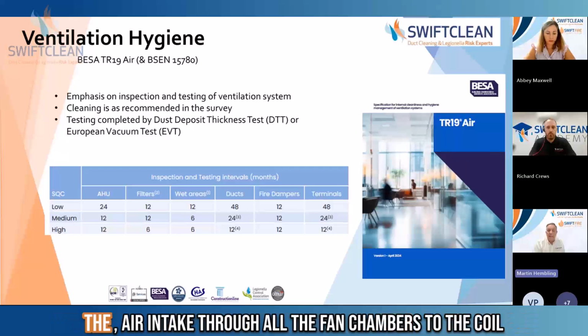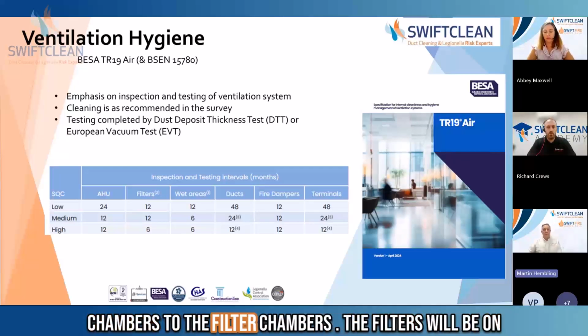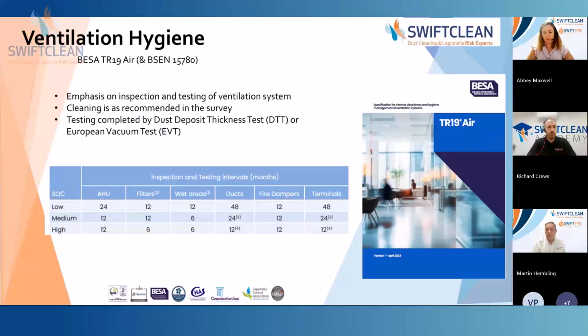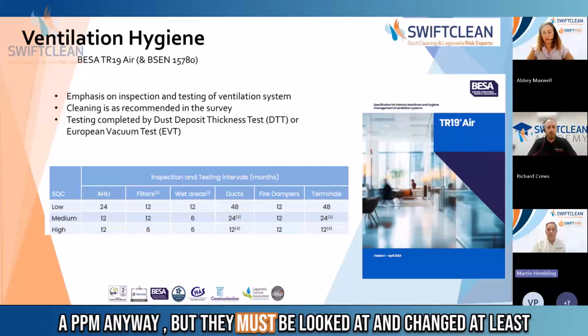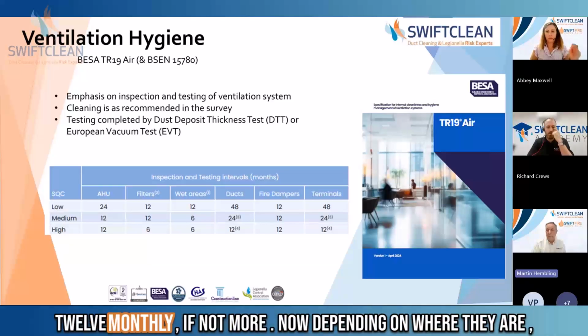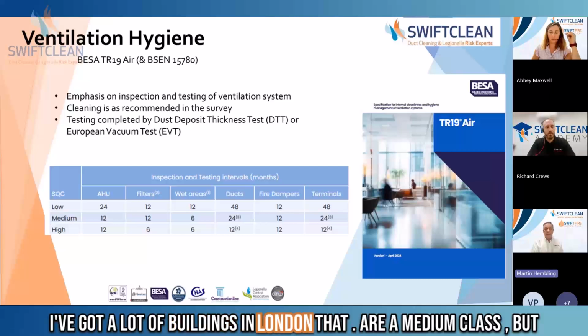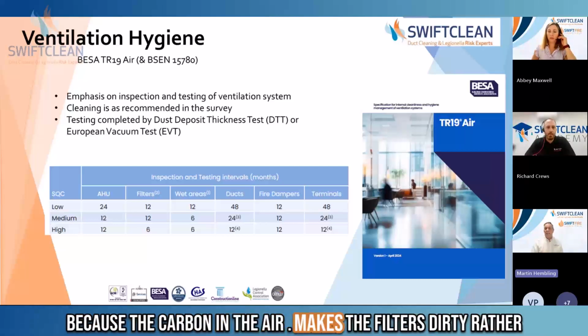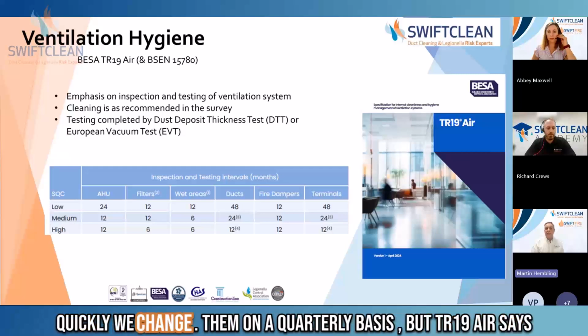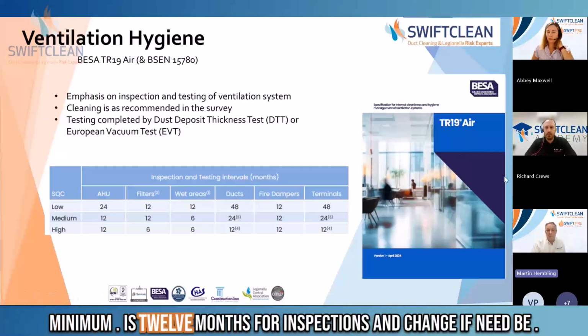So that will be the air intake through all the fan chambers, to the coil chambers, to the filter chambers. The filters will be on a ppm anyway, but they must be looked at and changed at least 12 monthly, if not more. Now, depending on where they are, I've got a lot of buildings in London that are a medium class, but because the carbon in the air makes the filters dirty rather quickly, we change them on a quarterly basis. But TR19 Air says minimum is 12 months for inspections and change if need be.